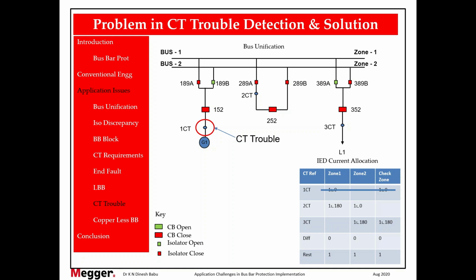This is point number one. Why should we not block the bus bar? If the bus bar is blocked, let's say there's a fault occurring at that situation. So, CT trouble followed by a fault. Then for a real fault, the bus bar would not be able to trip. Then how can we address this situation?